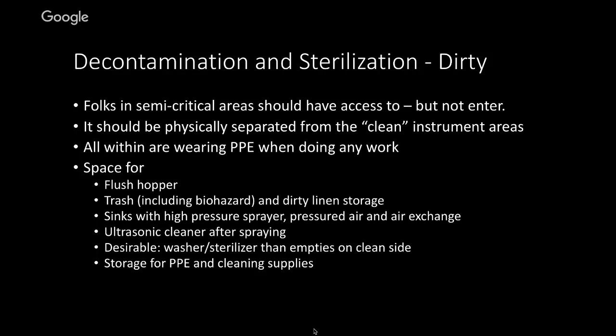Ideally, you'd have pressured air, because one of the things that you want to do is to get the water and all the stuff out of any of the joints or any of the cracks in the instruments. And the thing that we would do then, once the instruments are clean, is ideally put them in an ultrasonic cleaner after spraying. And once the cleaner has run, usually with a non-alkaline detergent and maybe with an enzymatic component to it as well, then you're going to put it into a washer sterilizer that empties on the clean side.